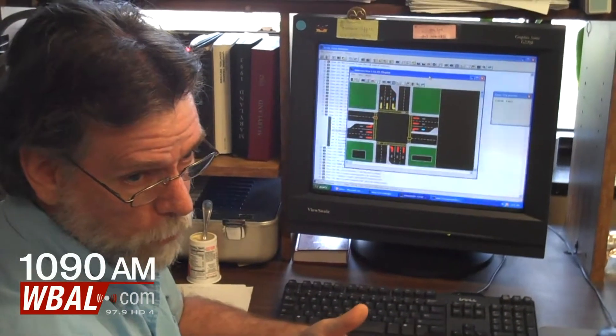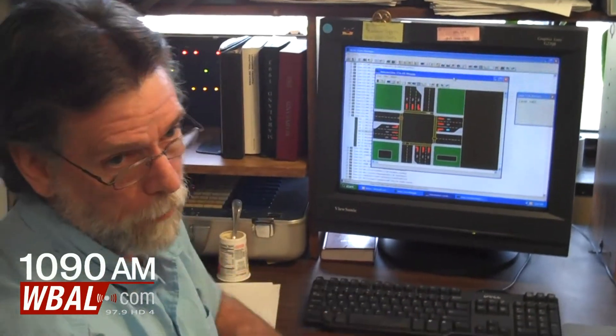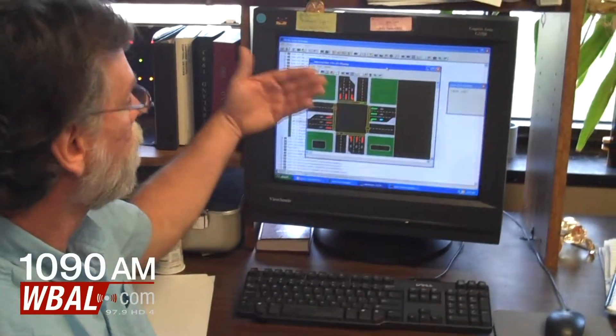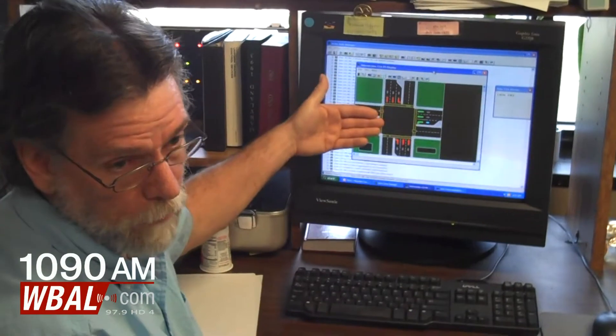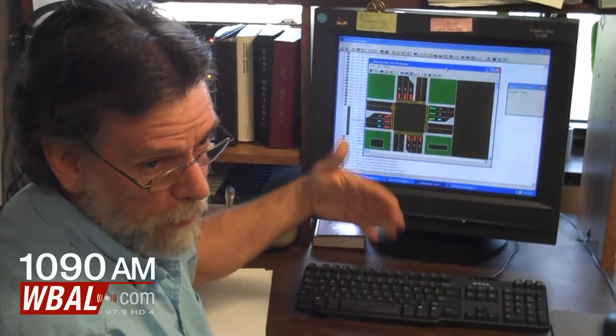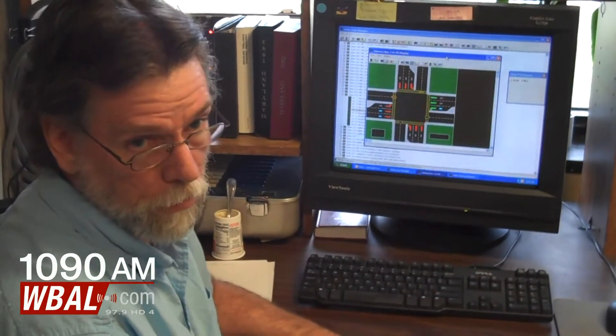If I can verify that it's working correctly — I'll give you an example. They call and say the side road is short timing. I can call this up, observe the loop detectors, check to see if it's timed to the proper max time, and then basically not even have to send a technician to the site.